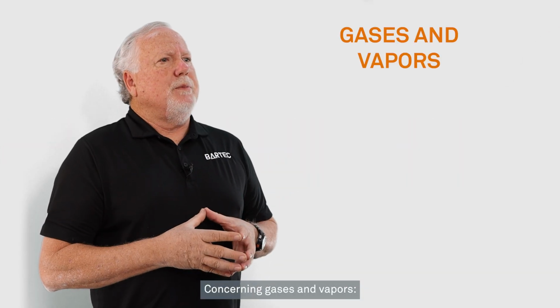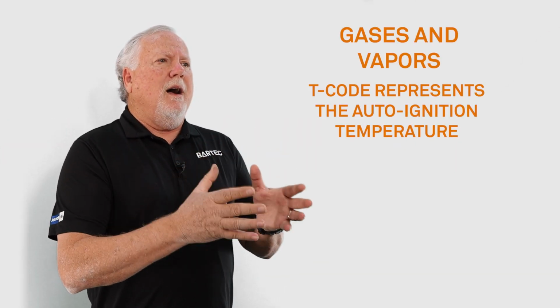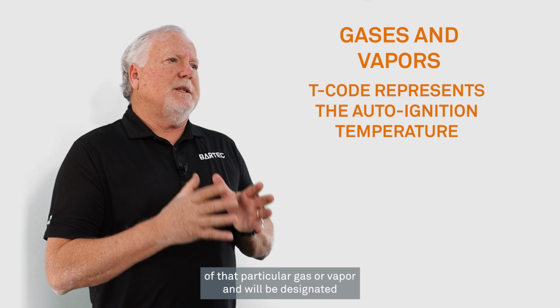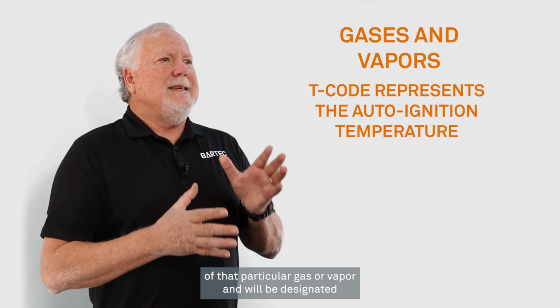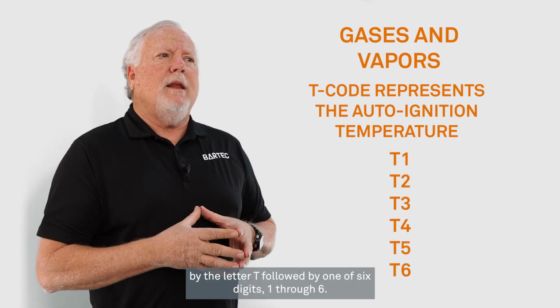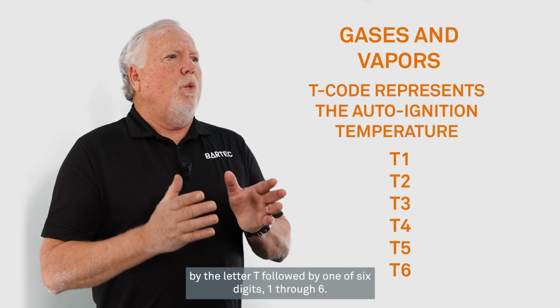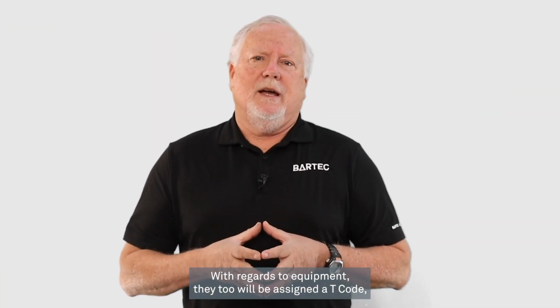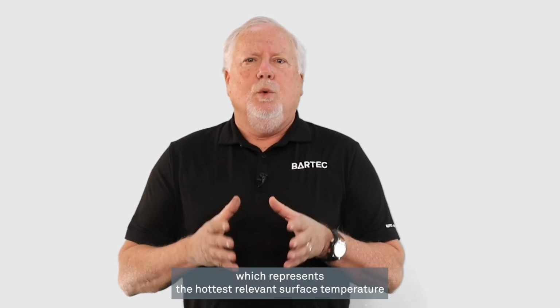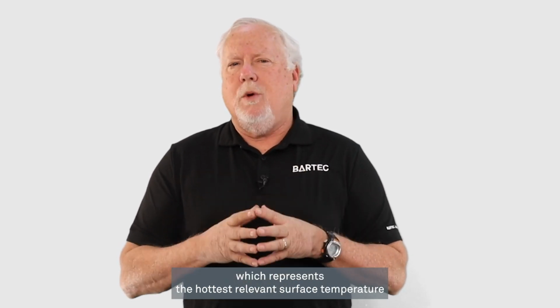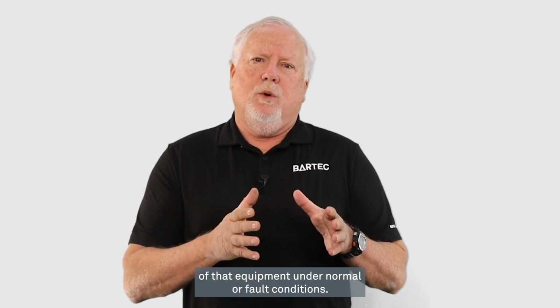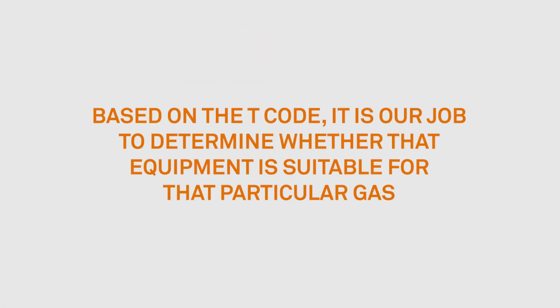Concerning gases and vapors, the T code represents the auto-ignition temperature of that particular gas or vapor and will be designated by the letter T followed by one of 6 digits, 1 through 6. With regards to equipment, they too will be assigned a temperature code or T code, which represents the hottest relevant surface temperature of that equipment under normal or fault conditions. Based upon the T code, it is our job to determine whether that equipment is suitable for that particular gas.